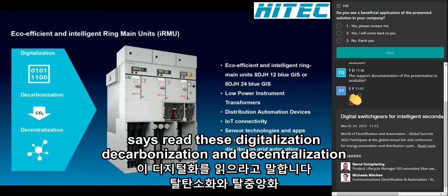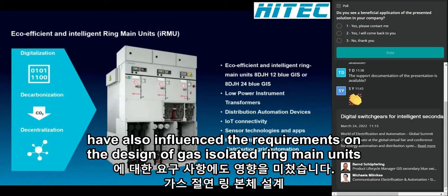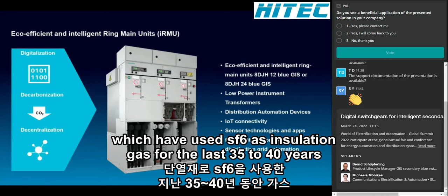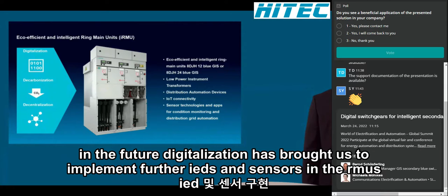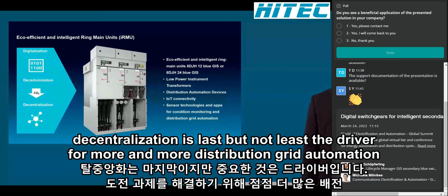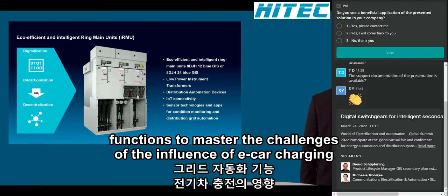Let's first have a look at the eco-efficient and intelligent ring main units from our 8DJH family. The 3 Ds, digitalization, decarbonization, and decentralization, have also influenced the requirements on the design of gas-isolated ring main units, which have used SF6 as insulation gas for the last 35 to 40 years. Decarbonization has pushed us to develop an alternative concept to prevent the use of SF6 in the future. Digitalization has brought us to implement further IEDs and sensors in the RMUs. Decentralization is last but not least the driver for more and more distribution grid automation functions to master the challenges of the influence of e-car charging and renewable energy supplies on the distribution grids.